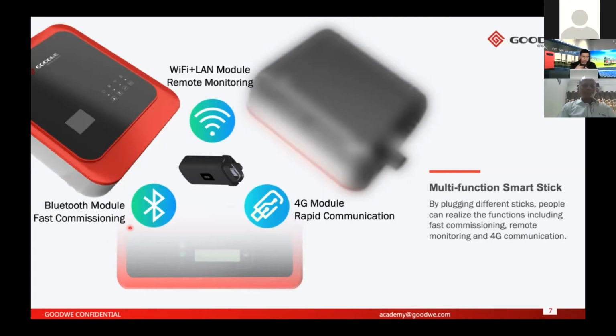Also we are going to have our Bluetooth module. The Bluetooth module is basically used for fast commissioning and local monitoring. Right now we use Wi-Fi, and for some special cases, clients will choose to use RS485. But basically, you will need to use Wi-Fi to do the commissioning job. But in the near future, we're going to publish our Bluetooth module. That means you will have a much more stable communication between your smartphone and the inverter, and it will make the commissioning more and more convenient, faster, and more stable for the installers. So that's our communication sticks.